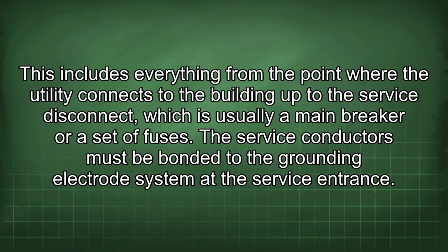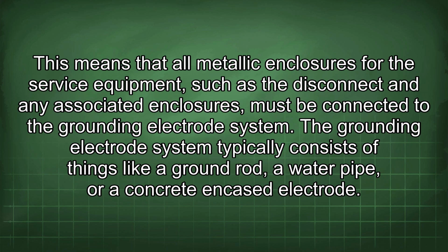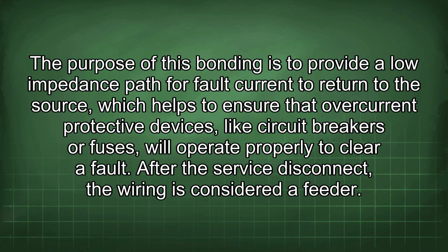The service conductors must be bonded to the grounding electrode system at the service entrance. This means that all metallic enclosures for the service equipment, such as the disconnect and any associated enclosures, must be connected to the grounding electrode system. The grounding electrode system typically consists of things like a ground rod, a water pipe, or a concrete encased electrode. The purpose of this bonding is to provide a low impedance path for fault current to return to the source, which helps to ensure that overcurrent protective devices, like circuit breakers or fuses, will operate properly to clear faults.